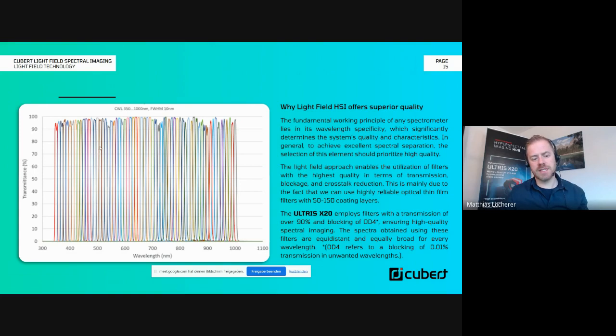This setup has an advantage, because typically the full width half max, which somehow defines the spectral resolution, increases with higher wavelength in, for instance, prism-based setups. In our setup, it's a constant 10 nanometers, which really allows a true equidistant band setting in very high quality, since we have an OD4 blocking, meaning we have less than 0.01% stray light effects on the camera.